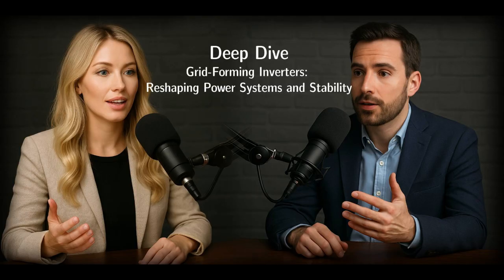What breaks? Several things become challenging. Standard overcurrent relays might not see enough current to operate reliably or quickly, impacting sensitivity. Coordination between protective devices becomes much trickier, ensuring the right breaker trips first. Distance protection, which relies on measuring impedance, sees a different source impedance from an inverter compared to a generator, requiring significant setting adjustments. Even current transformers need to be properly sized for these lower currents. It often requires a shift toward more adaptive or communication-based protection schemes.